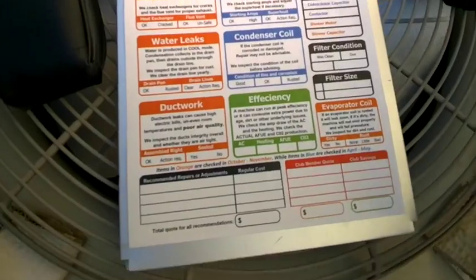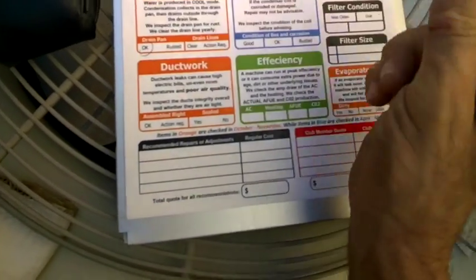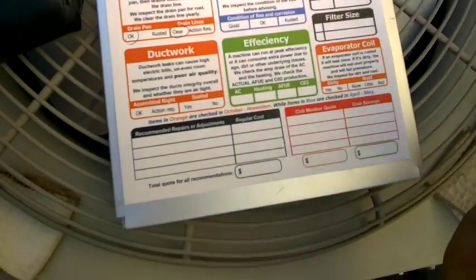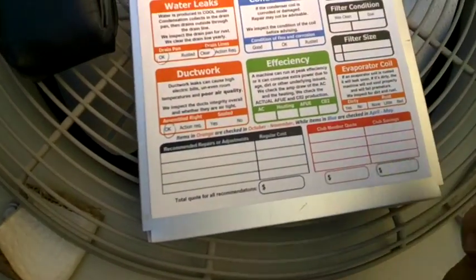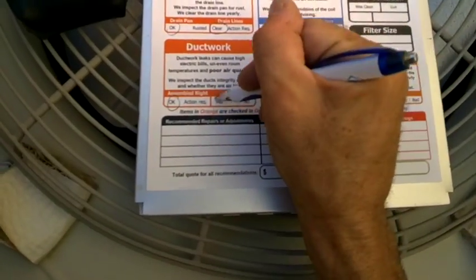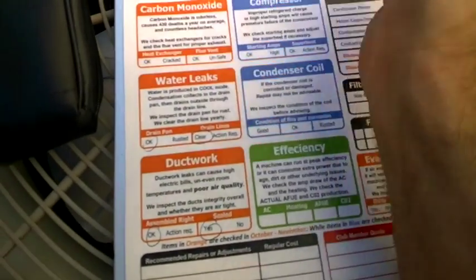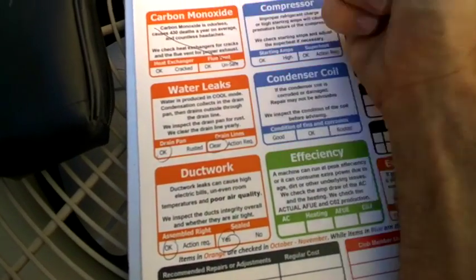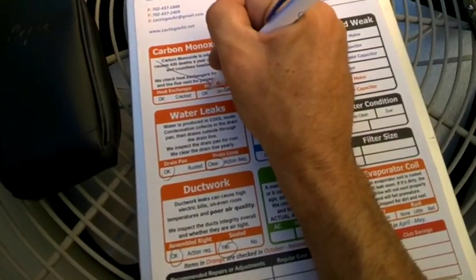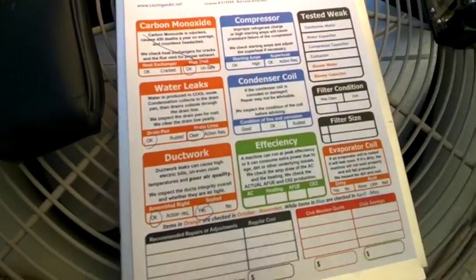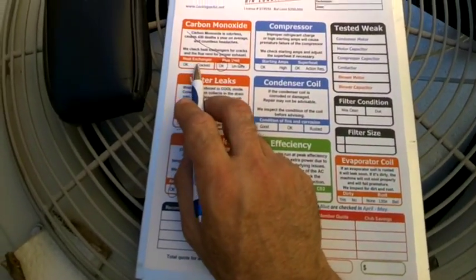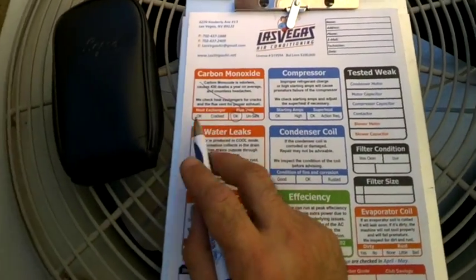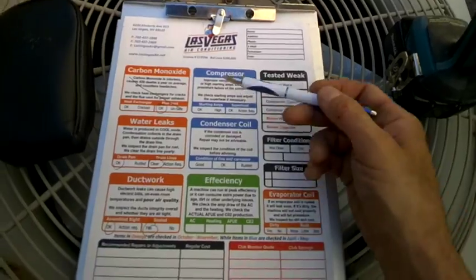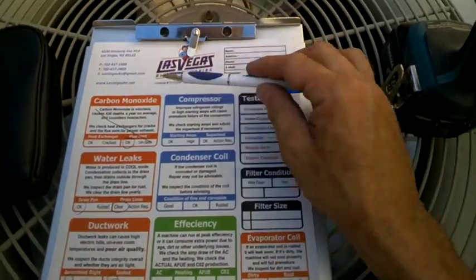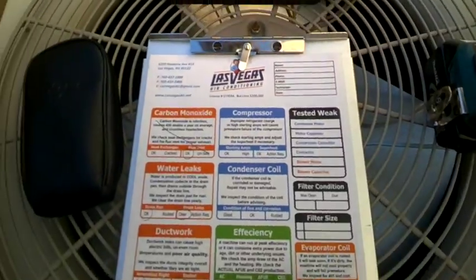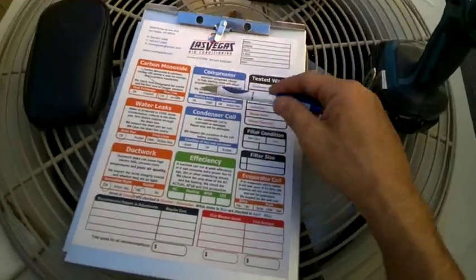As we were just up in the attic, we saw that drain pan was okay. Drain lines are clear. Ductwork is assembled properly. Sealed. Yes. Carbon monoxide. We're going to check that in the winter time, but I could see the flue was okay. So we didn't check the heat exchanger for cracks or carbon monoxide because we'll do that in the winter. But here we are outside at the air conditioner, so let's check the compressor or the condenser coil. We're going to go ahead and clean it up.